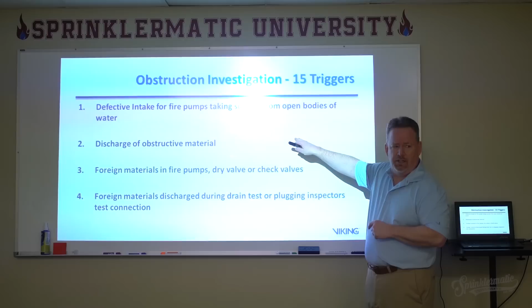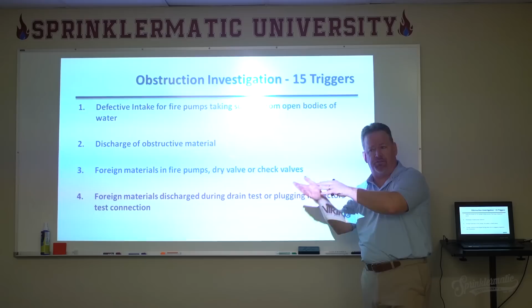That's quite different than an obstruction investigation. An obstruction investigation does not have a specific frequency to it. It has a triggering event. If something happens in or around my sprinkler system, I may have to do an obstruction investigation. And that obstruction investigation is pulling the system apart or running the camera up into the system to look for obstructive material. But where the internal assessment is every 5 years, there is no frequency for an obstruction investigation.